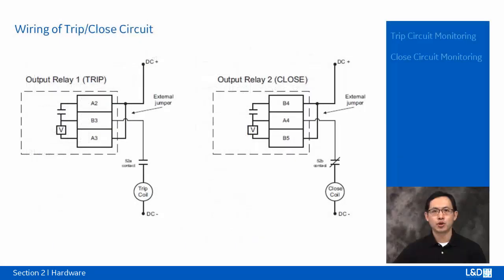A21. Breaker monitoring, including trip and close coil monitoring, is performed by a built-in voltage monitor on Form A output relays. Number 1 is for trip and number 2 is for close. The voltage monitor is connected across each of the 2 Form A contacts, and the relay effectively detects healthy current through the circuit. In order to do this, an external jumper must be connected between the terminals A2 and A3 for trip coil monitoring, and B4 and B5 for close coil monitoring. As long as the current through the voltage monitor is above the threshold of the trickle current, circuit integrity for the trip or close coil is effectively normal.